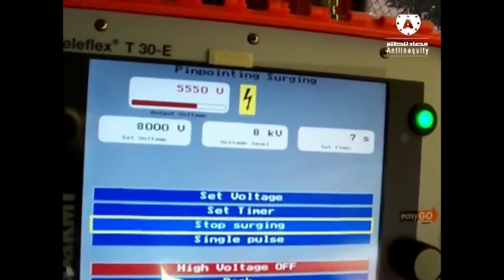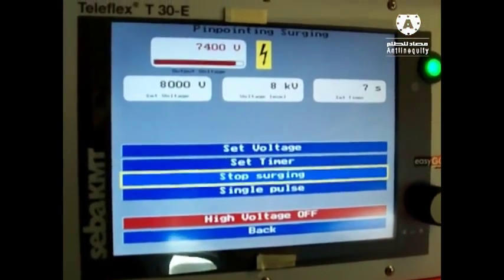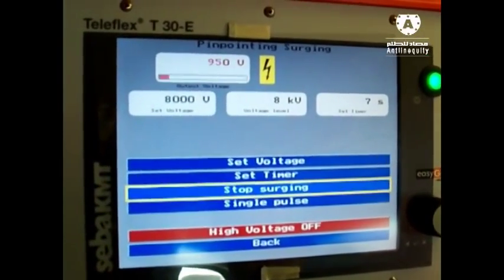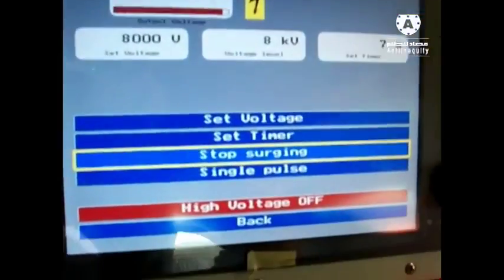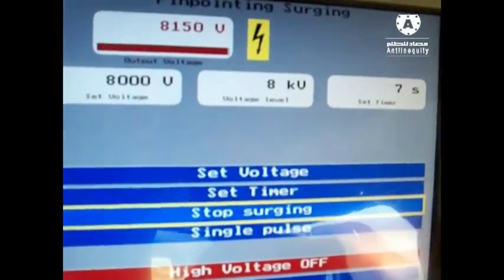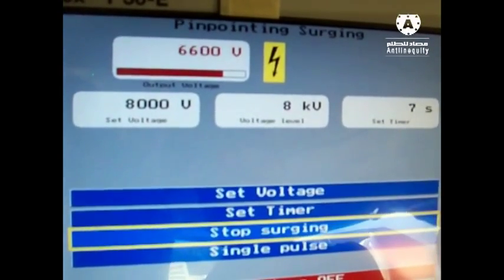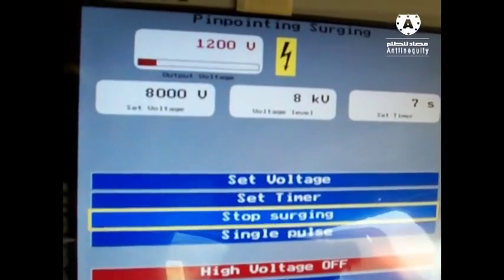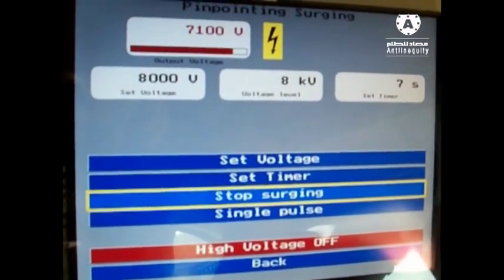Now we have to go out with the digiphone to the point where our TDR or arc reflection mode says that there is our failure, approximately 100 meters, 1 kilometer or more, and about 50 meters before our value we should start with our pinpointing, so that we are moving to our fault.